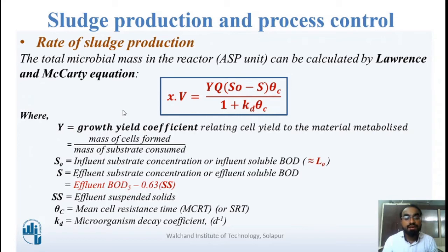So here is a term we have to understand about the S. S is the soluble BOD. It doesn't mean the total BOD. The BOD in the influent, we can say, is equal to the soluble BOD. That is what we are assuming. But after the treatment, what is the effluent which is coming out? It may not contain the biodegradable organic matter, that is our soluble BOD, but it may contain some BOD, that is my effluent BOD.